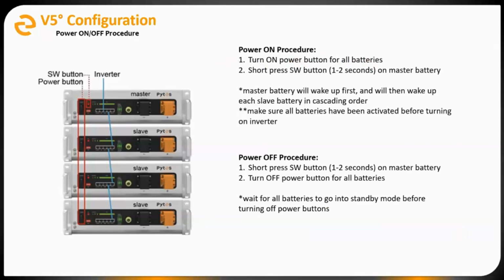You turn all those on, and then once they're all turned on, you do a short press and hold on the SW button. That's that red circle button on just the master battery. So 1 to 2 seconds, press and release. What you're going to see is the master battery will wake up first. It'll flash all its LED lights. You'll see it go into standby mode. It'll wake up battery 2, then battery 3, 4, all the way through the group.